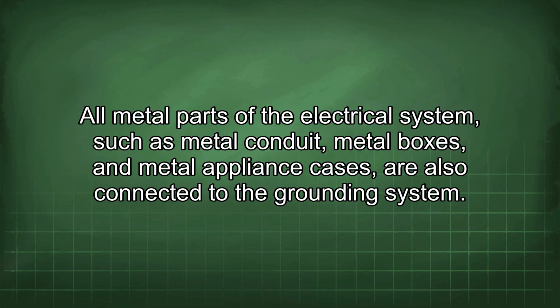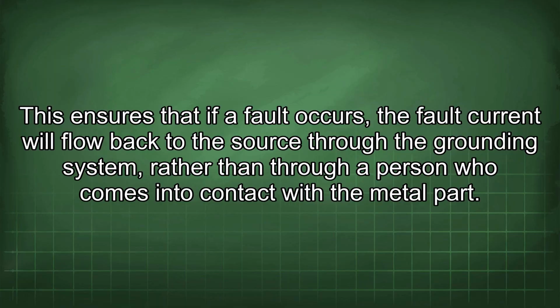All metal parts of the electrical system, such as metal conduit, metal boxes, and metal appliance cases, are also connected to the grounding system. This ensures that if a fault occurs, the fault current will flow back to the source through the grounding system rather than through a person who comes into contact with the metal part.